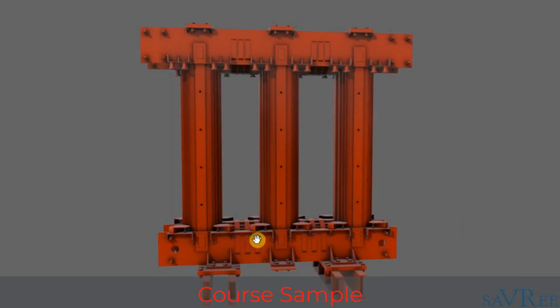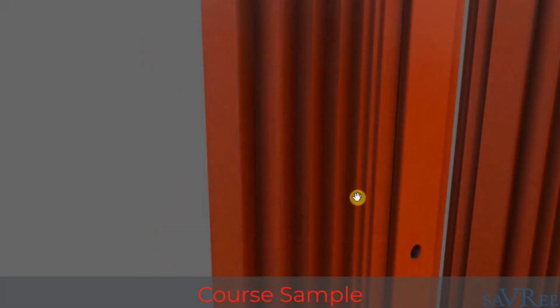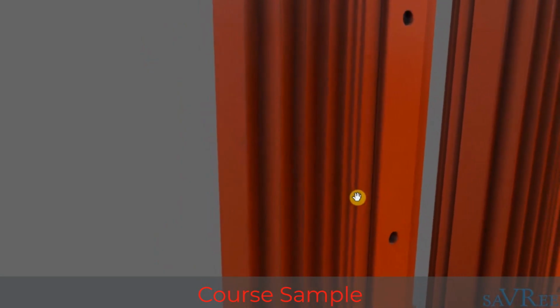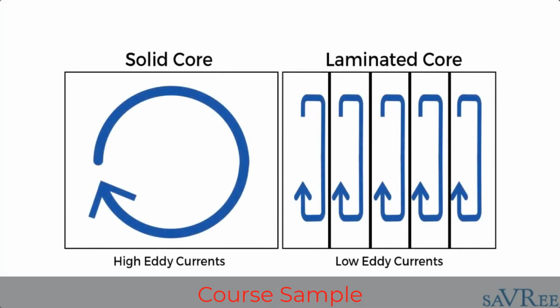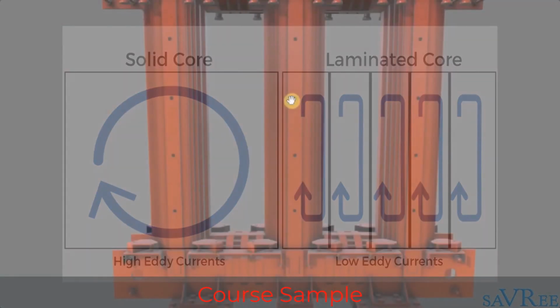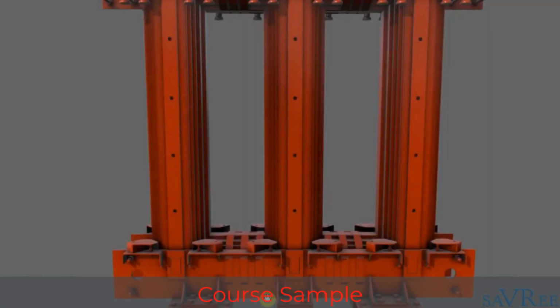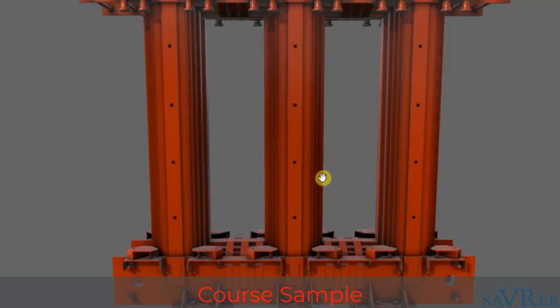The top and the bottom of the transformer core are known as the yoke. The reason we clamp these very thin laminate sheets together is because we want to reduce the hysteresis and the eddy current losses. So we'll clamp all of the metal sheets together to form a limb, and then we'll clamp the metal sheet pieces together to form the yokes, that is to say the top and the bottom of the transformer core.